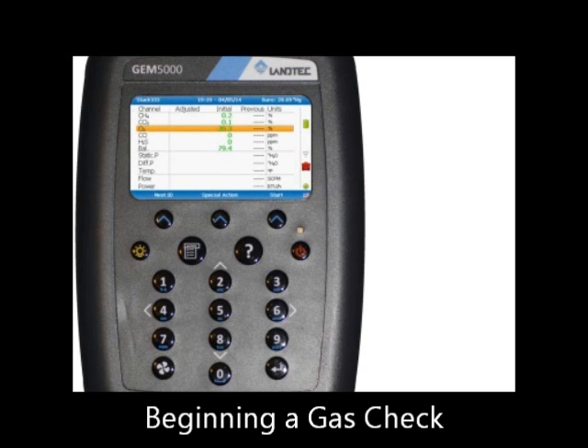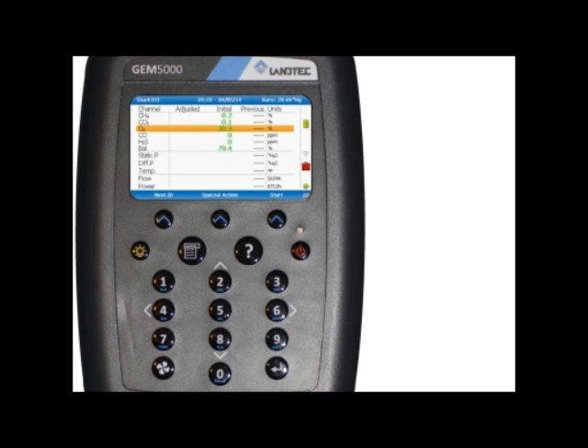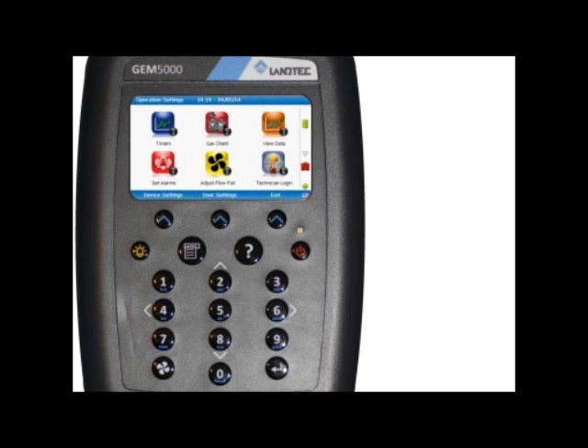This will take you to the main reading screen. So at this point, we will start by pressing the menu key. This takes you to the operation settings screen. From this menu screen, select key number 2 for gas check. From the gas check screen, press key number 1 for gas check again.